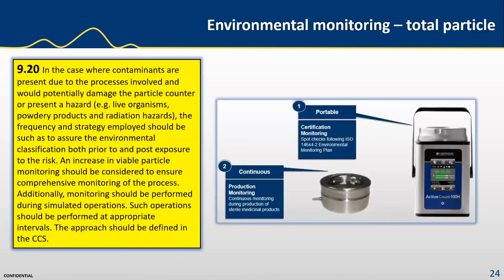Again, it says here, in the case where contaminants are present due to the process involved and would potentially damage the particle counter or air sampler or present a hazard, the frequency and strategy employed should be such as to assure the environment classification both prior to and post-exposure to the risk. And increased viable particle monitoring should be considered to ensure comprehensive monitoring of the process. Additionally, monitoring should be performed during simulated operations. Such operations should be performed at appropriate intervals, and the approach should be defined in your contamination control strategy.